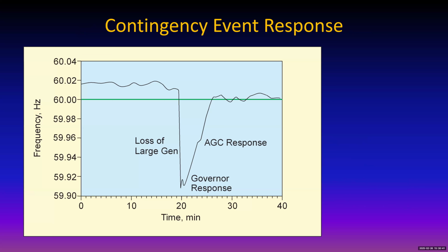Here's an example of what the picture might look like if you lose a large generator. The governor response is to apply more gas and try to speed things back up. But if we have to bring more generation online to get up to speed, then the AGC response comes in. In any case, you see here that within about 6 minutes we're back up to normal frequency.